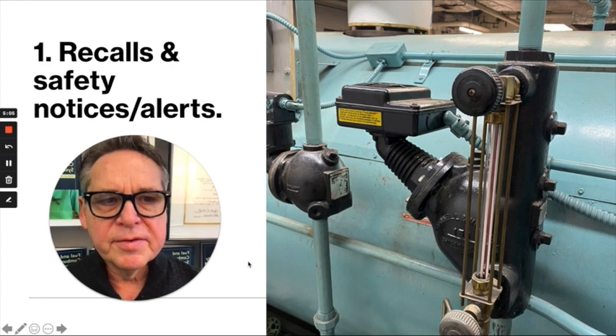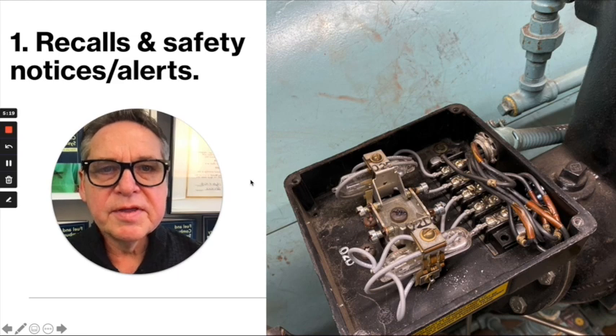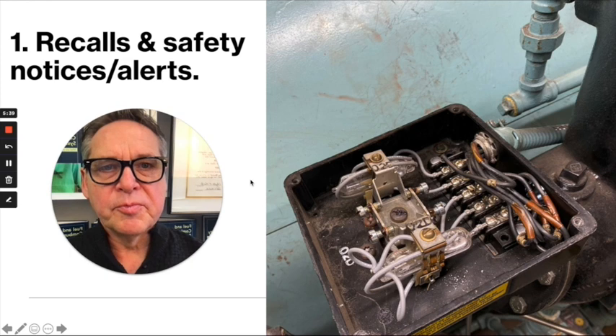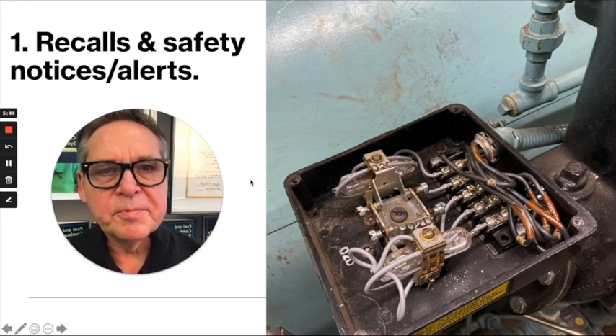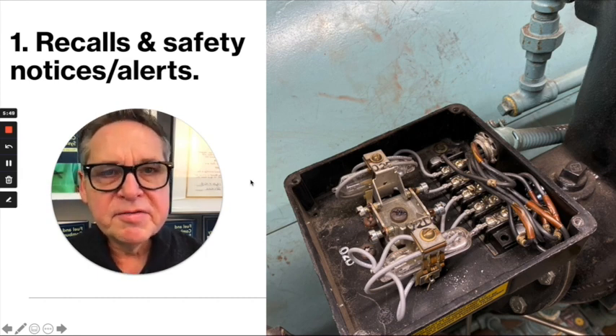Here's another example — not specifically about boilers, but this is a low water cutoff device attached to a water column. Inside this device there are mercury switches that make or break specific contacts. There have been recall notices submitted on some of these devices because of seals that keep water and steam from entering the switch area. I often open these up to check the model and serial number against the recall, and also to check for humidity or moisture damage within the chamber.